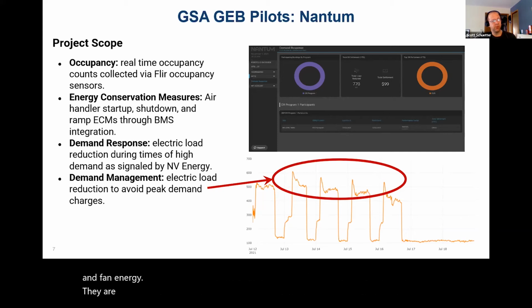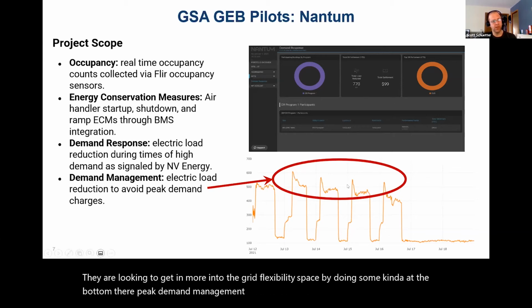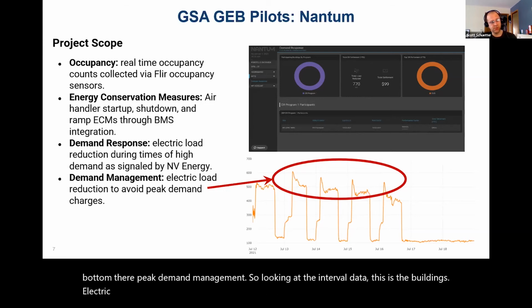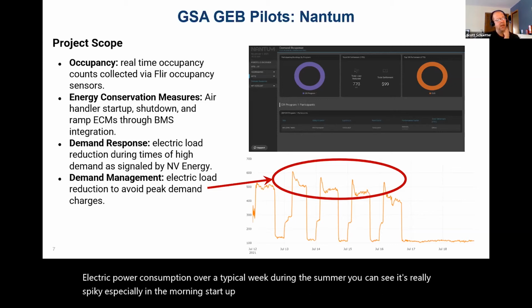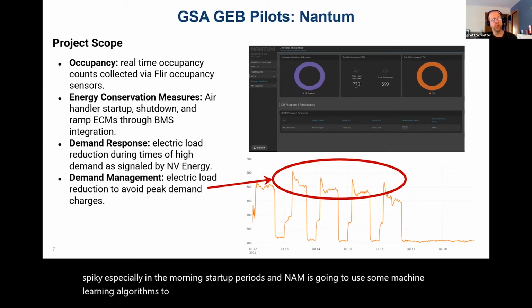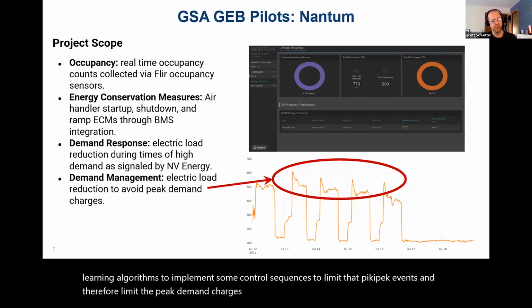They are looking to get more into the grid flexibility space by doing some peak demand management. Looking at the interval data, this is the building's electric power consumption over a typical week during the summer. You can see it's really spiky, especially during morning startup periods. Nantum's going to use some machine learning algorithms to implement control sequences that limit those peak events.